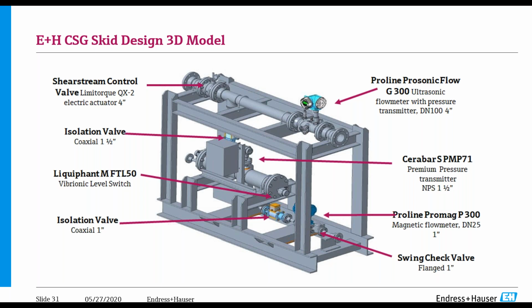You'll see there, as we saw on the P&ID drawing, that the inlet coming from the well on the gas line goes into our control valve, which is primarily there to control the flow of gas, but more so to control the startup of the well. We don't want to have the maximum flow rate right at the start of the well, because we need to manage the potential of collapsing wells, and we need to bring up the well in a controlled manner. It then moves on to go through our ultrasonic G300 flow meter, and Jason's touched on this a little bit in his presentation, but I'd like to go into it in a little bit more detail in this particular application. So the G300 actually offers many benefits in this application.